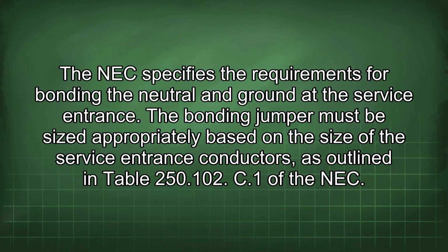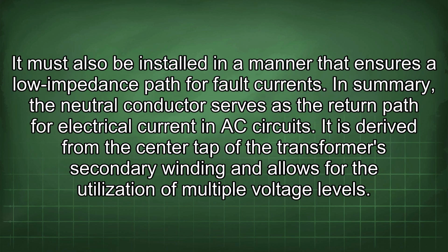The NEC specifies the requirements for bonding the neutral and ground at the service entrance. The bonding jumper must be sized appropriately based on the size of the service entrance conductors, as outlined in Table 250.102(C)(1) of the NEC. It must also be installed in a manner that ensures a low impedance path for fault currents.